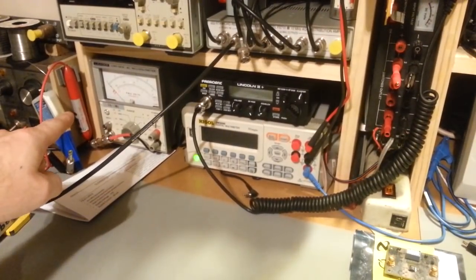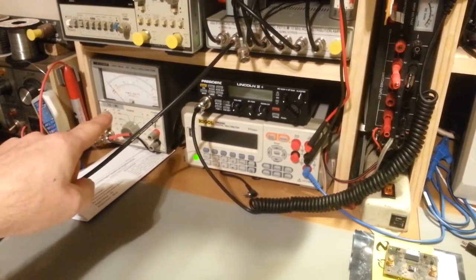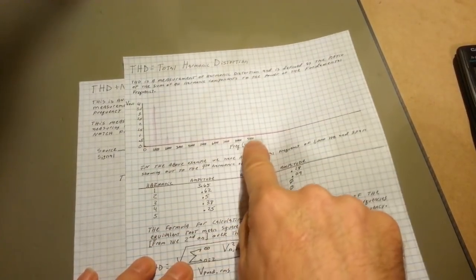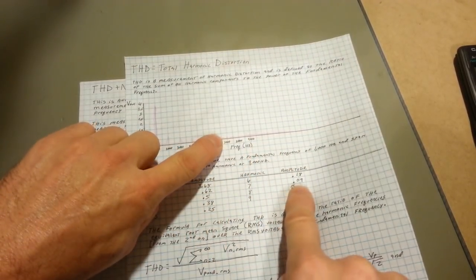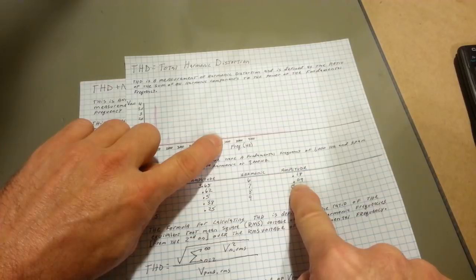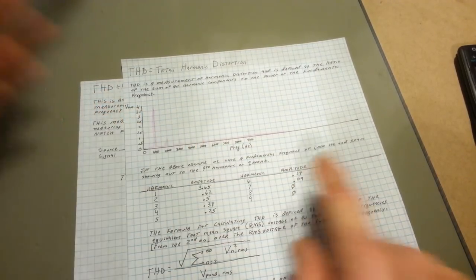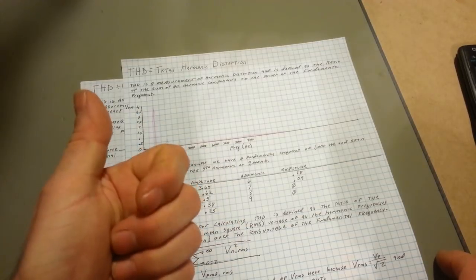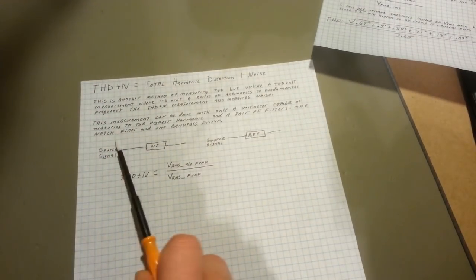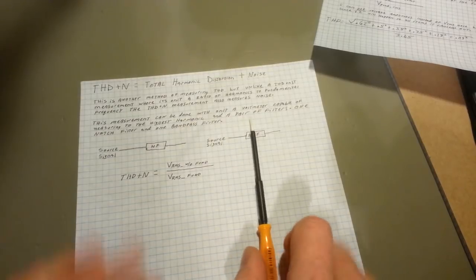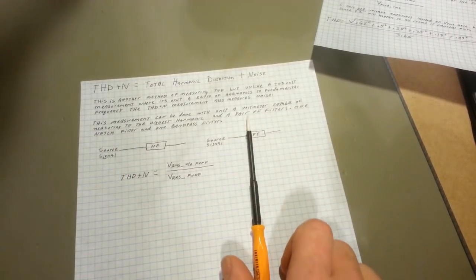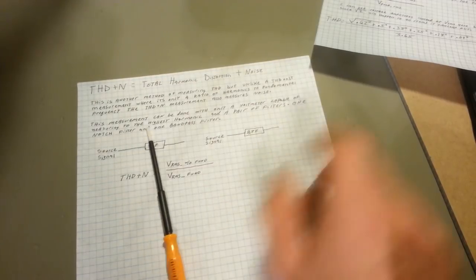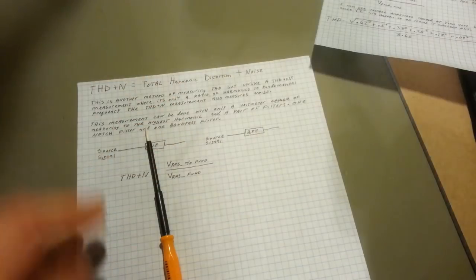So, actually, that voltmeter right there would be fine, because actually I even have a label on there. That meter can accurately measure from 5 hertz to 1 megahertz. So, in the case of measuring this signal here, the highest frequency, actually only the 7th, because that's the highest harmonic where there was still measurable voltage, is only 7,000 hertz. So that meter is perfectly fine. 7,000 hertz, that one over there measures to 1 megahertz. To the highest harmonic. And now, the only problem is you also need a pair of filters for this, because that's what this does. So, and this one is kind of a good comparison to the SINAD measurement, where it's using a filter.